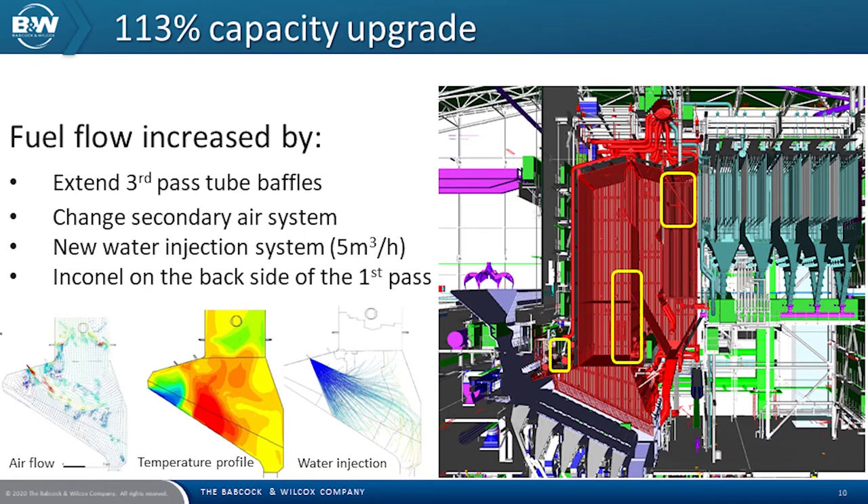On the boiler, we made several changes to handle the increased fuel flow. The tube baffles in the third pass were extended to ensure the temperature did not go too high before the convection section. The secondary air system was changed to achieve a better burnout by extending the time for particles inside the furnace. A water injection system was installed for better combustion control overall.